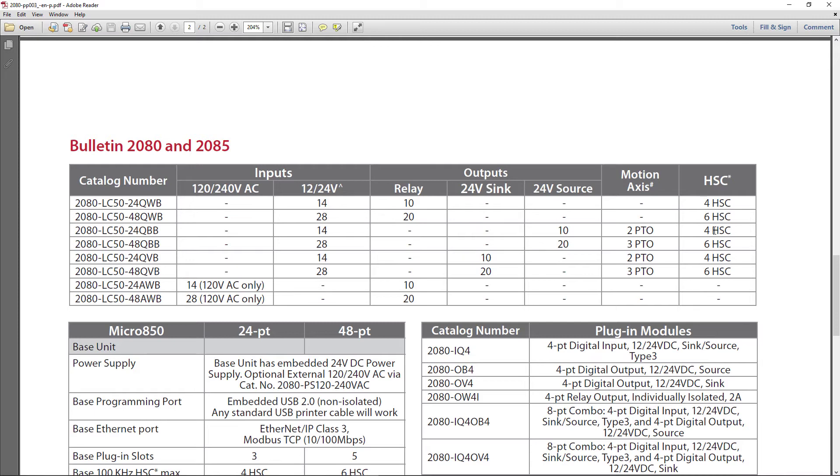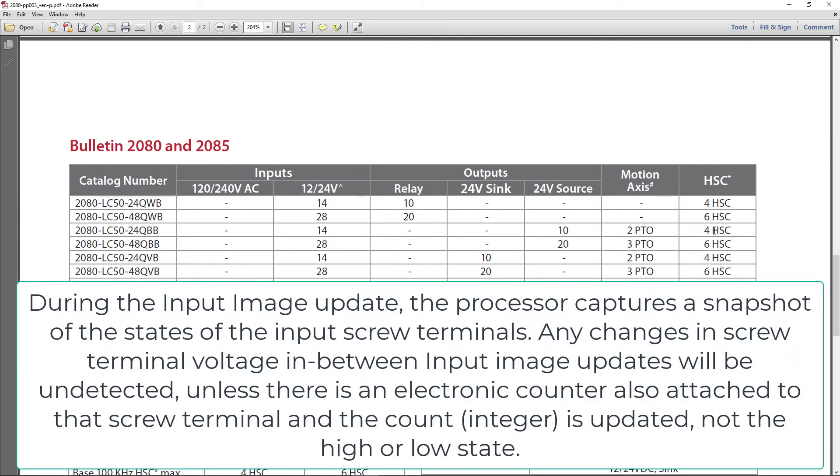Remember, the processor scans the inputs, executes the logic, and then transfers the outputs out, but we'll just say that there is a scan time. In other words, so if you had a real high-speed pulse coming in, 15, 20, 70, 75 of them could come in in between scans. You would lose all those counts.